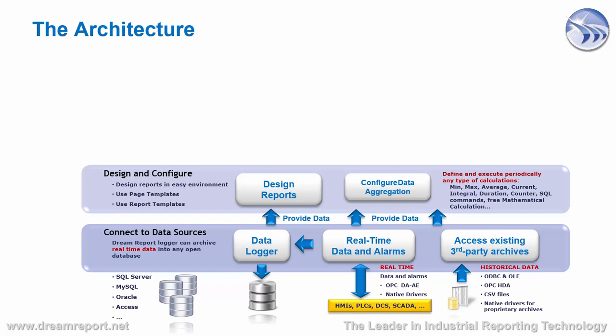For instance, you might have a series of flow meters that you'd like to totalize on a daily basis. Using DreamReport's data aggregation engine, you can pick those tags, set a daily frequency, tell DreamReport to use an integral, and then record those values on a daily basis back into its own database. At that point, those aggregated values are available to use in any other reporting object in DreamReport.